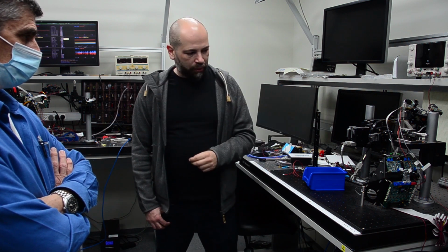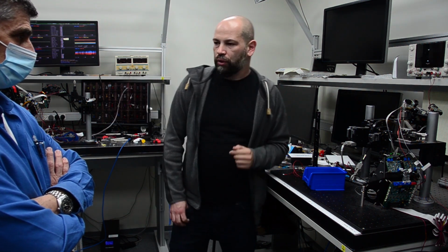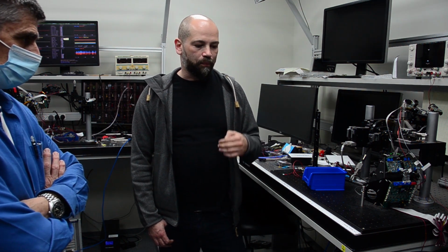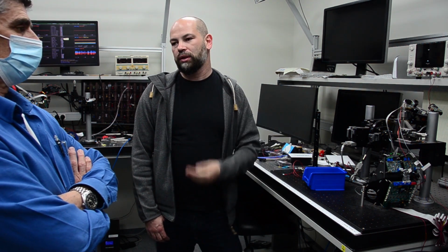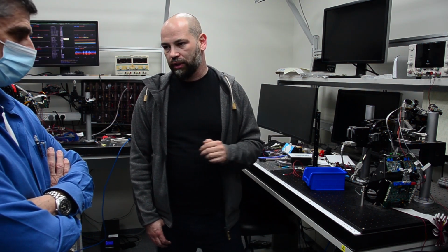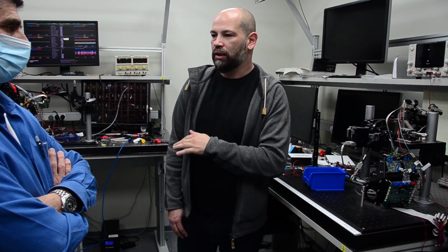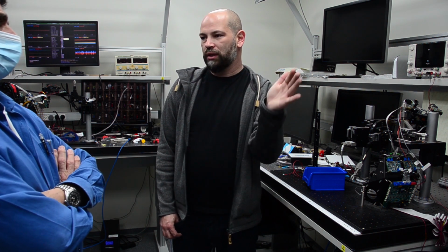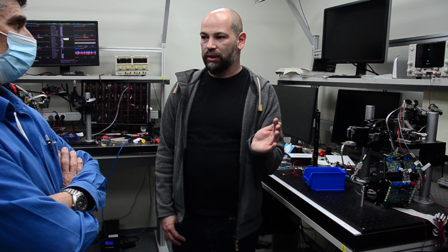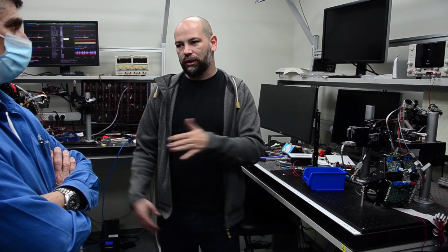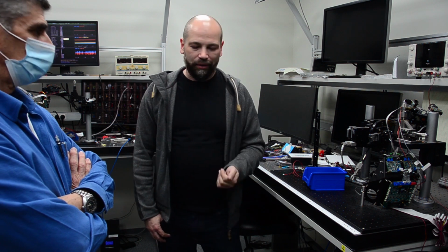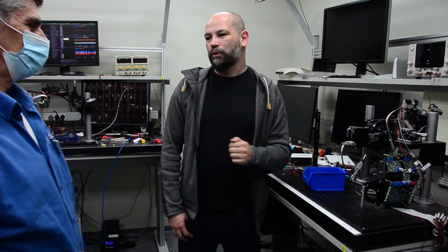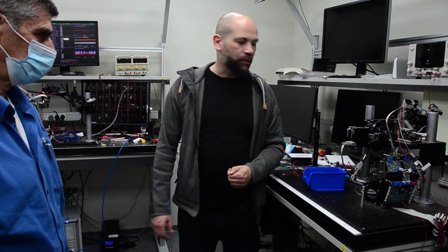In this early prototype, the reason we use it till now, we have also integrated the green laser, which is coaxial with the IR laser, and we were at the beginning assuming that it would be fine for the user to ignore the laser. However, what we found out, since the optical axis and the visual axis are not on the same axis, the person would see the image, the spots somewhere at the side, and would try to follow it, and eventually, since the eye cannot do a 360-degree turn, we would completely move the eye to the periphery of the human vision.